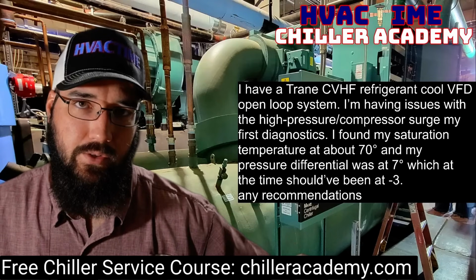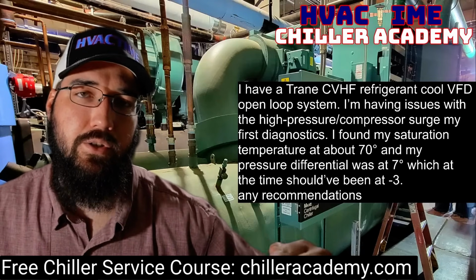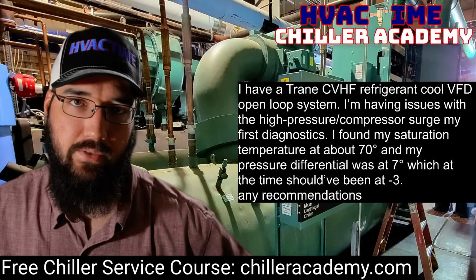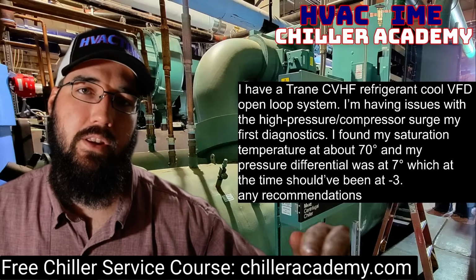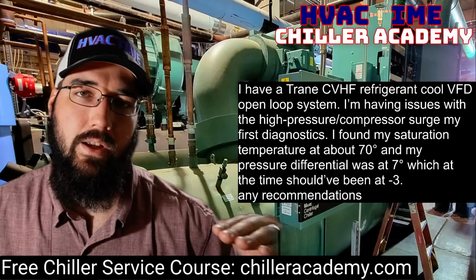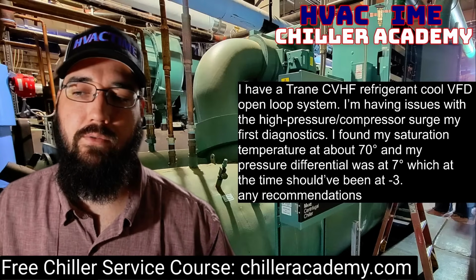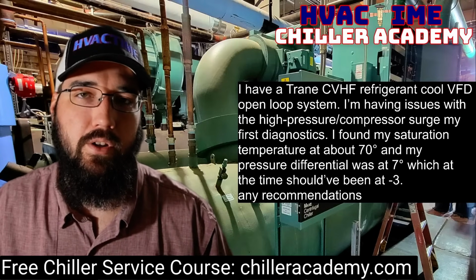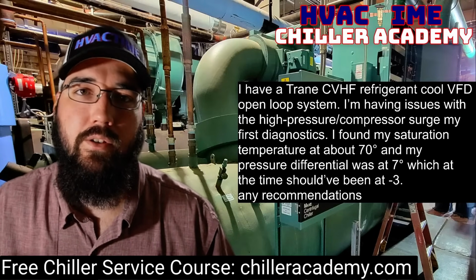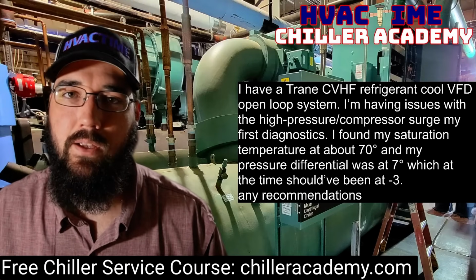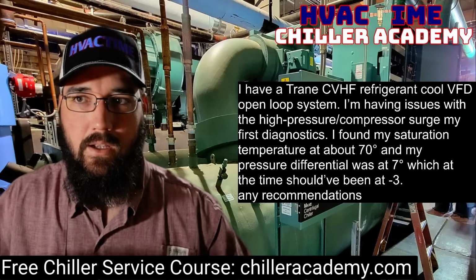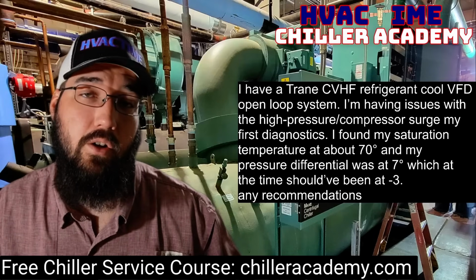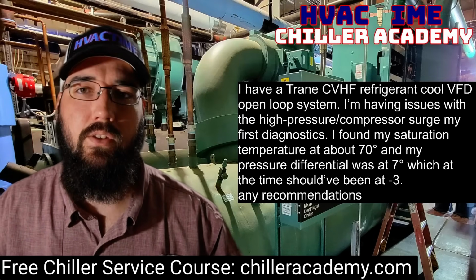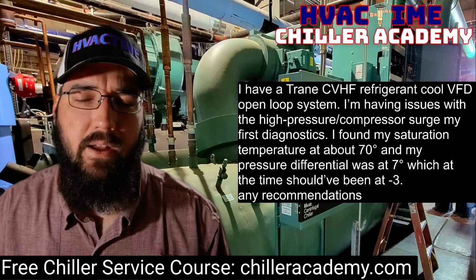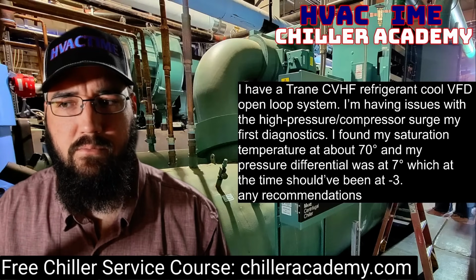What I would rather see is that my pressure differential, even if the pumps are in hand, fine, leave them in hand. I'd rather see that my DP across the condenser is within range. And if you don't know, if it's a smaller tonnage, somewhere in the 3 to 5, 6 PSID has been kind of a baseline for your smaller, less than 1,000 ton machines. And as they scale, that's going to change a bit. That would be one of my first points.